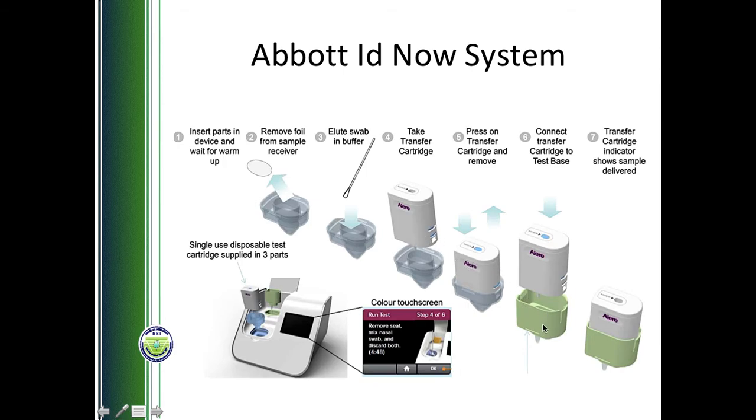It goes into the test chamber. The test chamber has a test tube beneath. Everything goes into the machine, and that will carry out the reading. Remember, the principle is isothermal amplification. The entire thing can be carried out in the span of 10 minutes. So within 10 minutes, we get the result of whether the specific virus sequences are present or not. This is the system by Abbott.